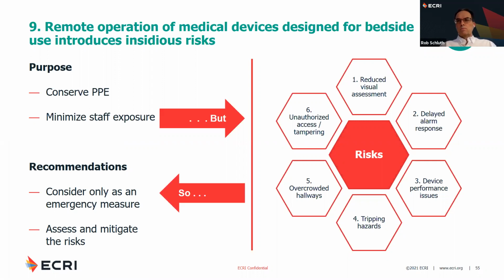The third item, device performance issues. So with things like the infusion pump example that we showed, you have all the tubing running from the device into the patient. That's longer tubing than you would normally use, so that could affect things like flow rates. For a lot of intravenous infusions, that's not going to be a big issue, but for medications that you have to very carefully titrate, that could cause a concern. So operating the device at a distance may not be appropriate in that circumstance.